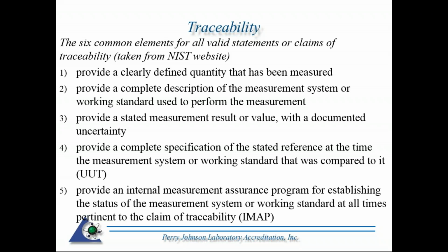Number 3, by definition, the measurement uncertainty. So the non-accredited source would have to have a stated measurement uncertainty. That would be reviewed. It needs to be reasonable, and may even warrant an investigation as to what were the actual uncertainty contributors that went into that.